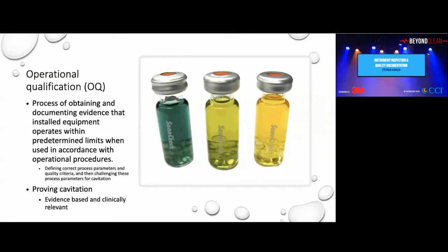So you will get your manual, you'll get it there, and you'll read it. Hopefully, they will tell you how to check for cavitation. Let's say they don't - you will then go to your OQ, the process of obtaining documented evidence that the installed equipment operates within predetermined limits in accordance with operational procedure. If you bought a sonic and just installed it, and didn't check it for cavitation, how do you know it's really working? And when it breaks down, this is where the OQ comes in.